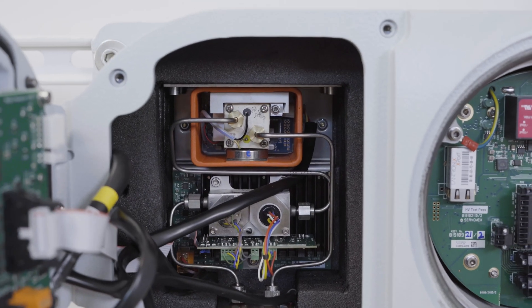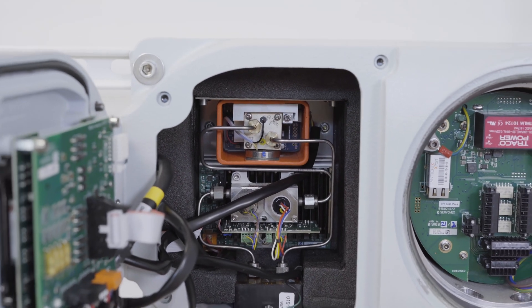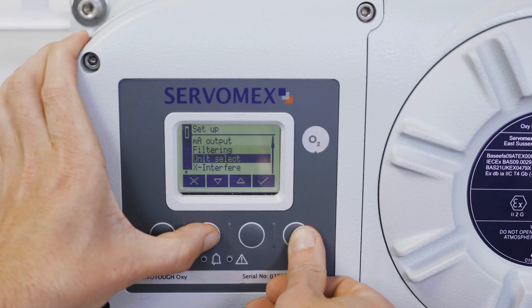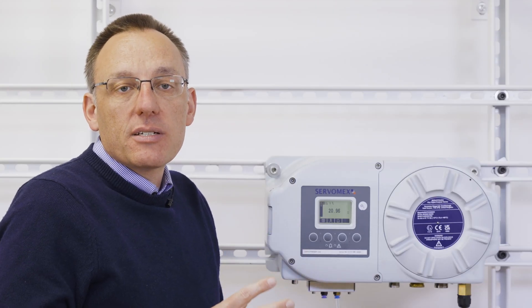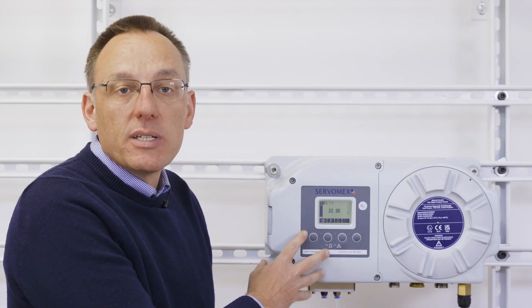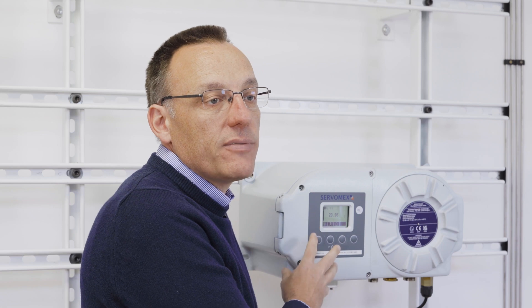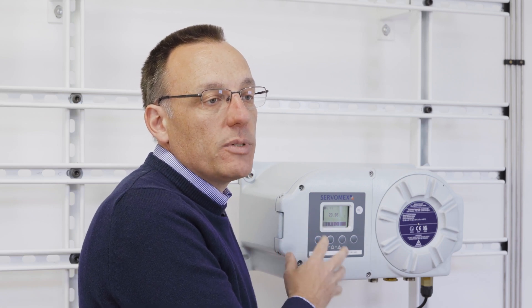The sample compartment contains intrinsically safe electronics including the LCD display and the interface keypad. The paramagnetic transducer and associated sample pipework is all contained within. The design minimizes the internal pipework to the transducer delivering a fast measurement response time with a T90 typically less than 6 seconds. The sample compartment is also thermally heated to approximately 65 degrees centigrade as standard for optimal measurement performance.